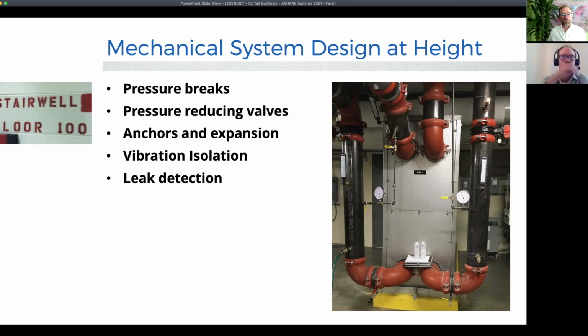So buildings often have heat exchangers for pressure control to keep the piping systems in certain ratings. When you're in the design phase doing design reviews, or even in the submittal review, you want to look to see if it's rated for the correct level of pressure that tier of the building is going to have. The engineer should know how to do this correctly, but it is something that can slip through the cracks.